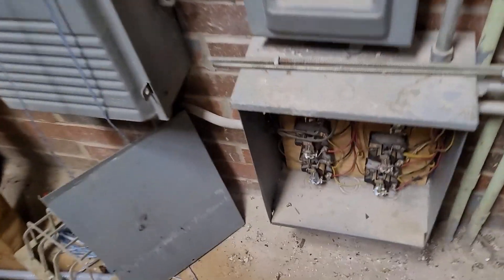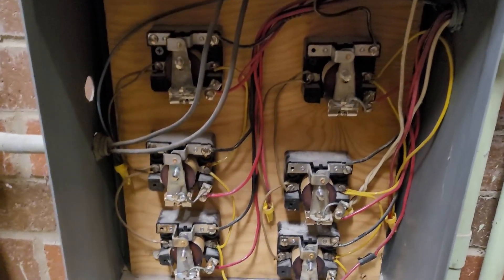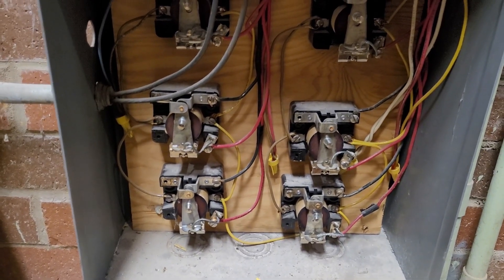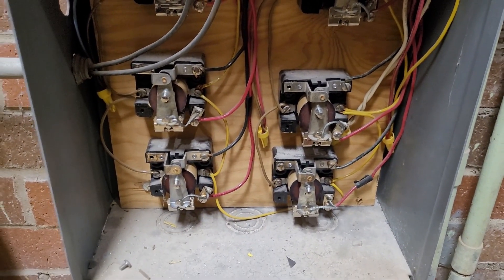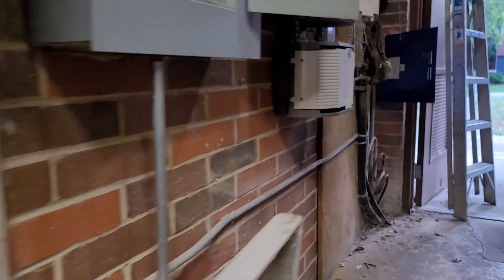I find this box — the box is full of super old relays. I think, aha, there's probably six groups of thermostats on a red wire control. Then I'm looking at where the control for these relays comes from. You've got these conduits going out that way — this one just goes up to the breaker box, so I don't care about that.